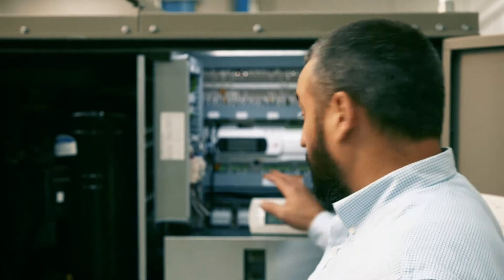We've put this on retry logic so the first alarm the compressor will shut off and then will automatically restart but if you get two out of envelope alarms within 60 minutes it locks out the cooling. You'd get that alarm over the BMS or through the handheld and then the customer would have to come and clear the alarm and investigate what the problem was.